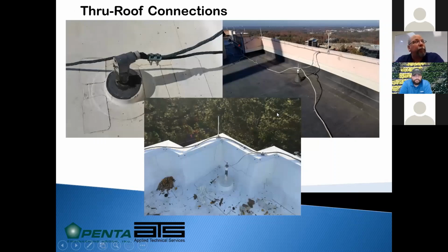And then our Thru-Roof connections, because the preferred method for most building owners is to have the lightning protection go down through perimeter columns. NFPA and UL want those conductors to be as near as practical to the outside edge of the building. We aren't wanting to bring that energy in through the core of the building and then have to take it back out again. So this can be just a pitch pan with raw cable going straight through. It's very tough to waterproof a stranded cable. So we have a Thru-Roof assembly, which is a threaded rod going through PVC. So we have a cap and different waterproofing details. This is more of a standard electrical part, not really approved for lightning protection.